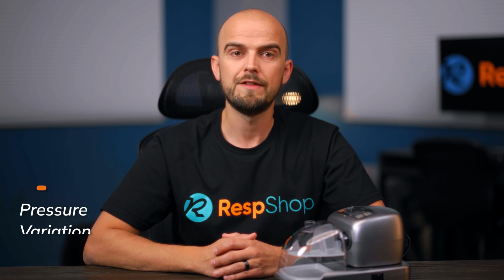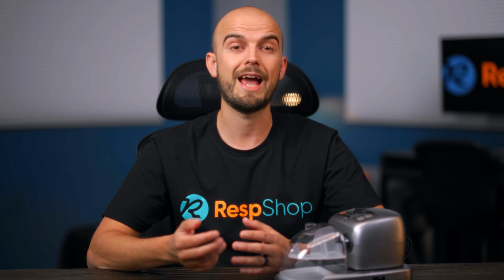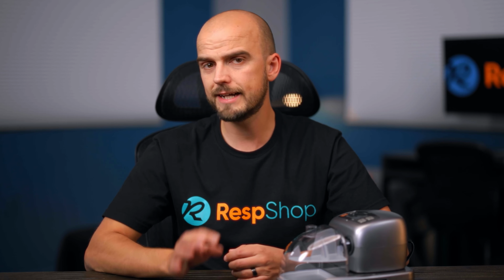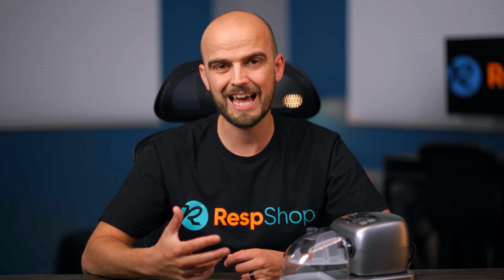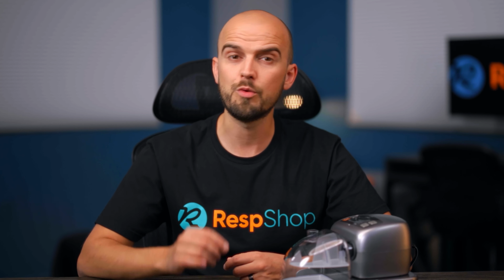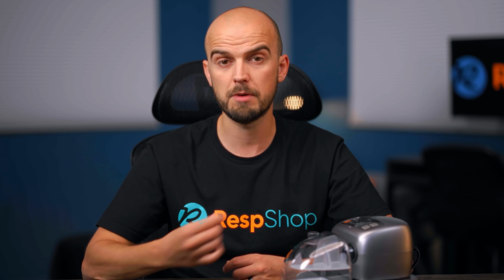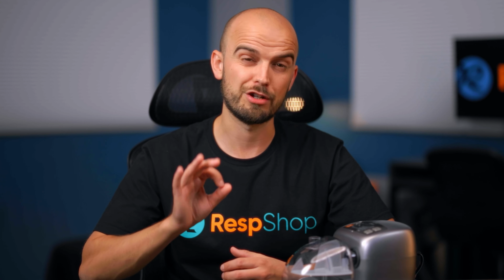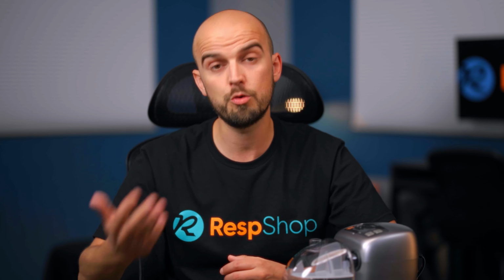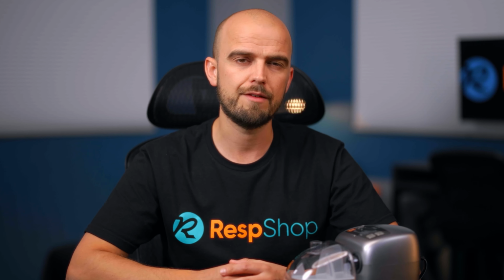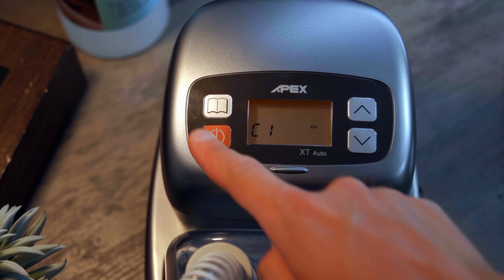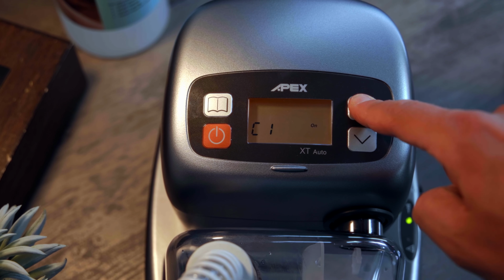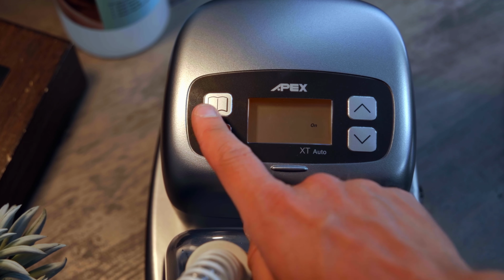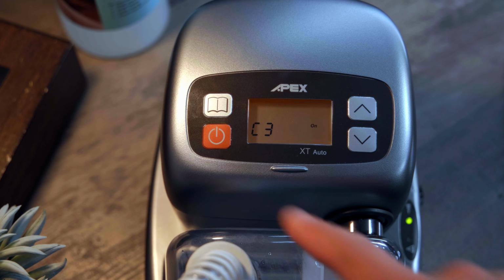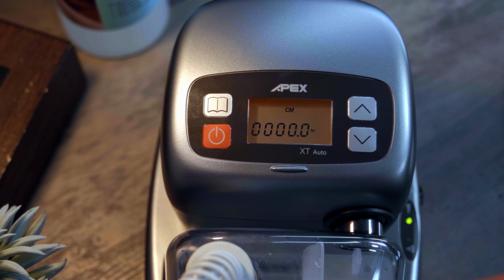If this is turned on, then the air pressure will vary depending on whether you are exhaling or inhaling. The idea here is to drop off the pressure when you exhale to make it easier for you, as you won't need to breathe out against a higher pressure coming into the mask. The level of pressure relief can be set from 0 to 3, where 3 is the greatest pressure relief and 0 is no pressure relief. As this is a comfort setting, feel free to adjust this to suit your needs. You can do so by pressing the up or down arrows to select the level you prefer, then press menu to confirm. The next menu item is CM, which stands for Compliance Meter.